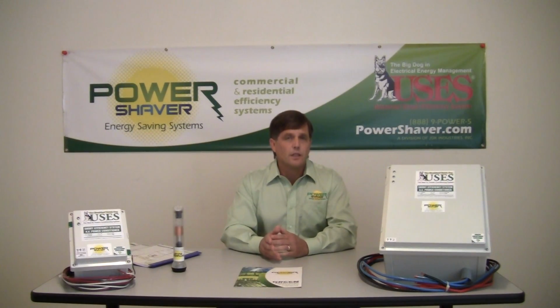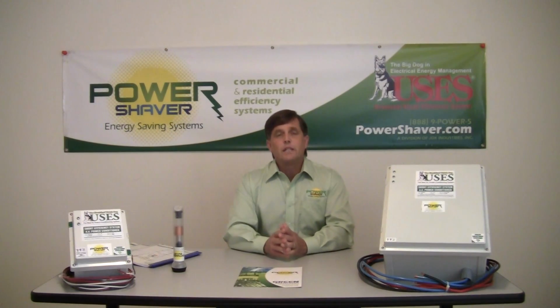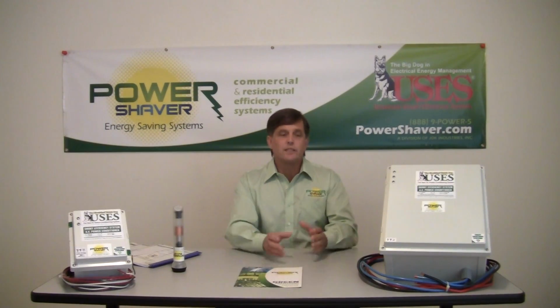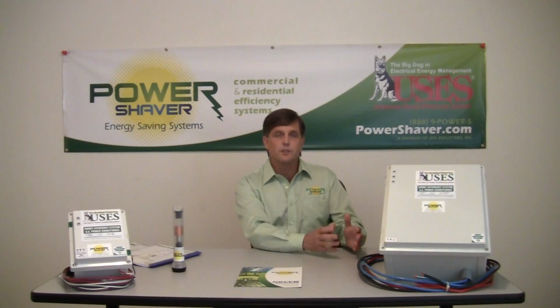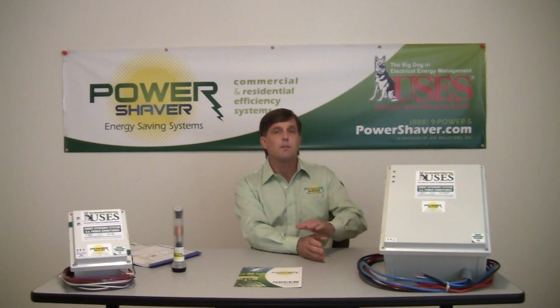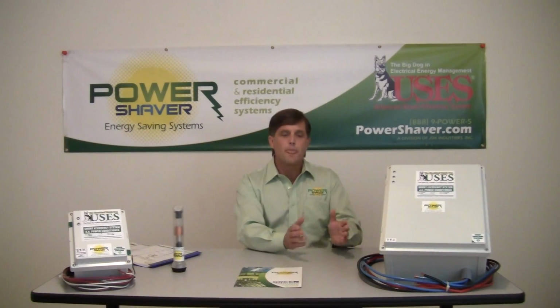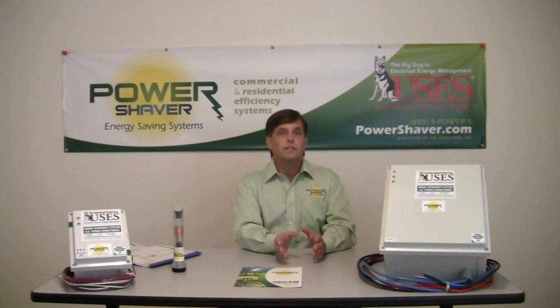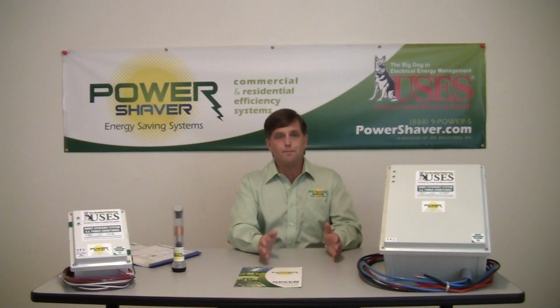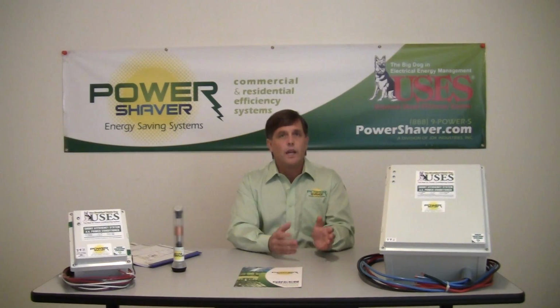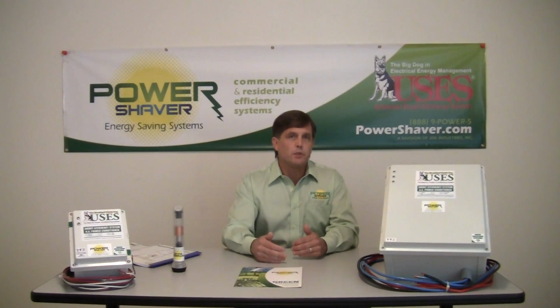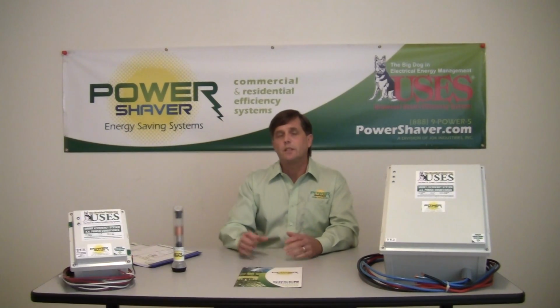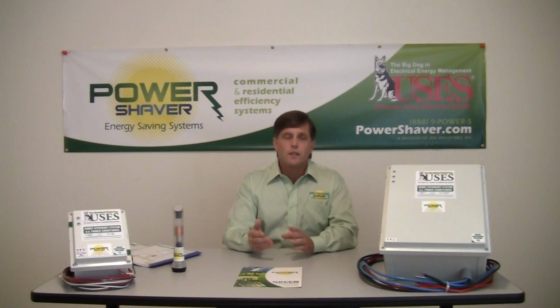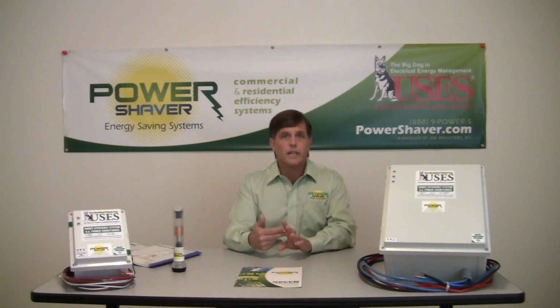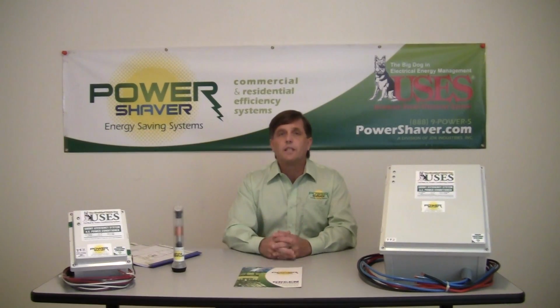The installation of these devices in your facility is specific because they are power generators, power conditioners, and surge protectors. They are specifically and intentionally placed from the service entrance to protect you from surges, spikes, sags, phasing problems. Our product has standby power for several cycles because of how it operates. 5 nanosecond response time because it is a non-thermal protection device. The remaining devices, if more than one, would be installed at the major distribution panels and motor control centers throughout the facility based on how your power is distributed. They're connected in parallel via a breaker per National Electric Code or other types of connections.